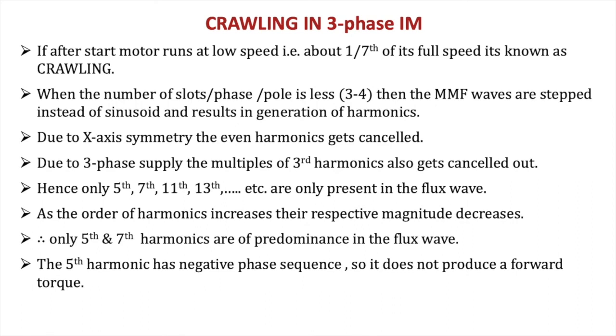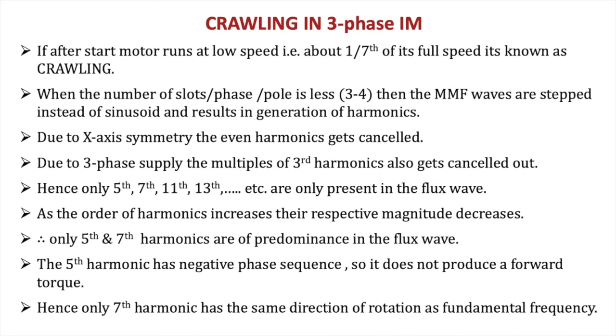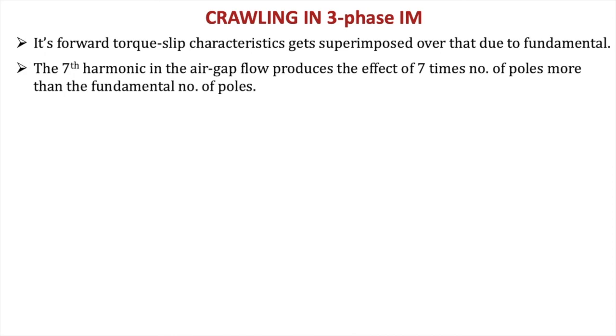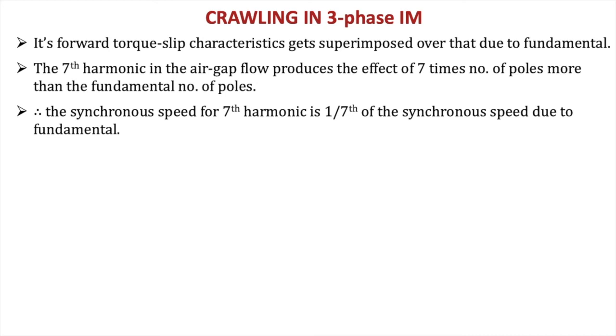But the 5th and 7th are predominant in the flux wave because their magnitudes are more than the 11th and 13th and higher harmonics. The 5th harmonic has a negative phase sequence, so it does not produce a forward torque. Hence, only the 7th harmonic has the same direction as the fundamental, and therefore this forward torque slip characteristic gets superimposed over that due to the fundamental. Therefore, the 7th harmonic in the air gap flux produces the effect of 7 times the number of poles of the fundamental. If the number of poles is more, the speed reduces. Hence, the synchronous speed for the 7th harmonic is 1/7 of the synchronous speed due to the fundamental component.